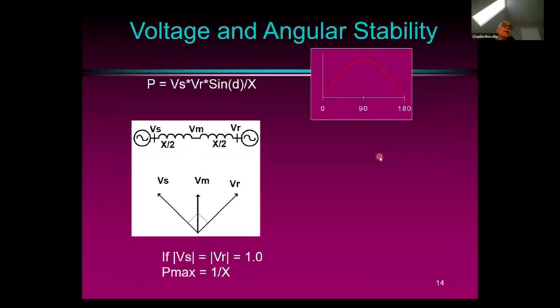Also, angular stability can be affected by the amount of reactive power you have. So if we have a voltage at the sending end of a power system equal to 1 per unit, and a voltage at the receiving end equal to 1 per unit, then the maximum power deliverable will be when the angle between these two voltages is 90 degrees. And the maximum amount of power will be 1 over X.